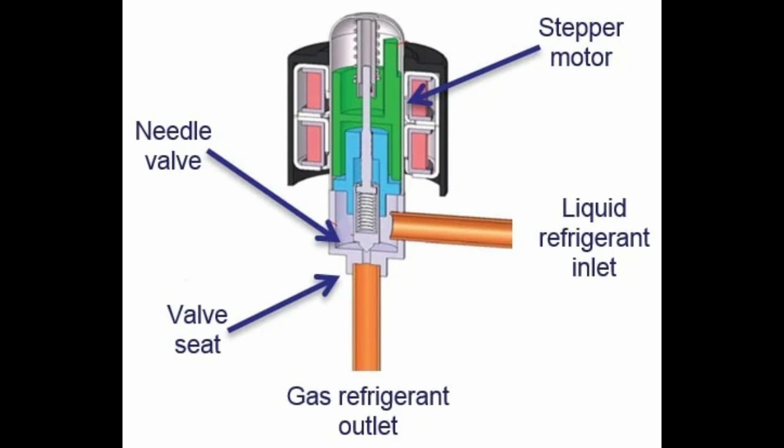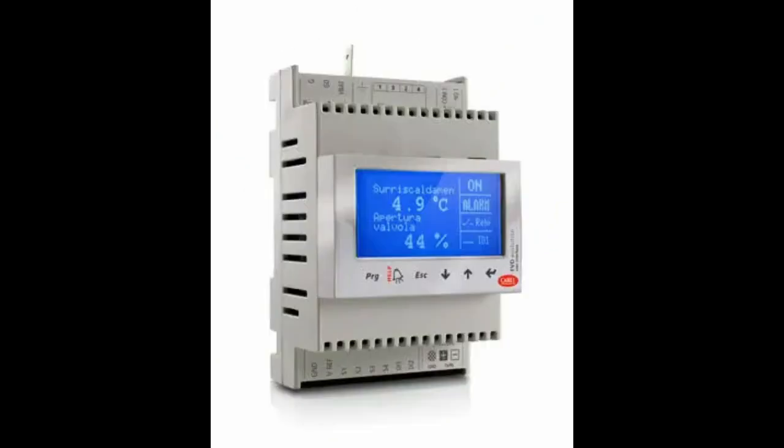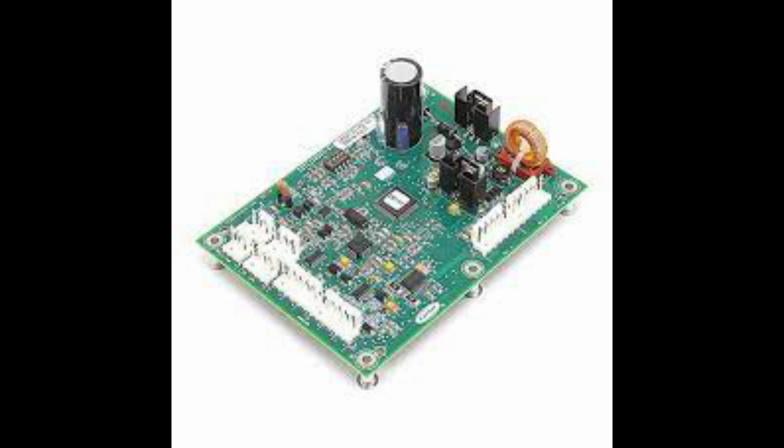The EEV works by using a stepper motor or solenoid to open and close the valve, allowing more or less refrigerant to flow through it. The opening and closing of the valve are controlled by an electronic control unit (ECU), which receives input from various sensors such as temperature and pressure.